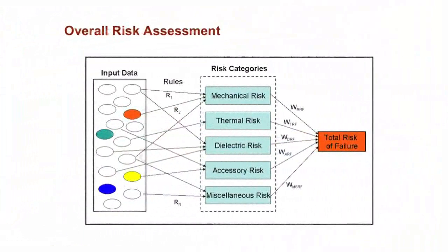So the overall idea is, you want to calculate a risk of failure for a transformer. And you have all these different input data, like DGA and test results, information you know about transformers and so on. And each of these contributes in some way to all the different risk categories of a risk of failure assessment. So of course, it's how it applies to each factor and what rules you use. That's the backbone of a risk of failure calculation. But the end goal is to get one number, like some percent risk of failure per year for a transformer.